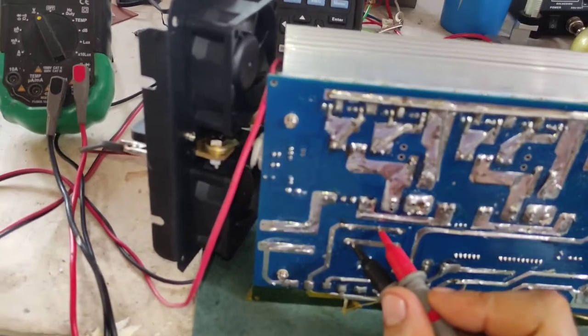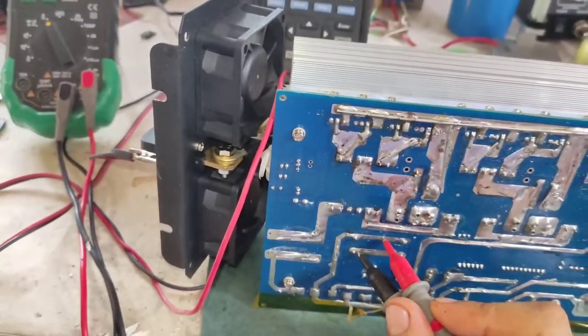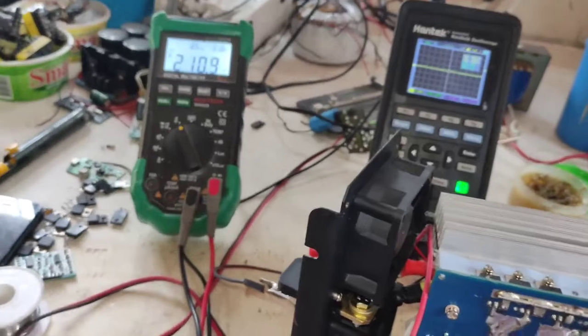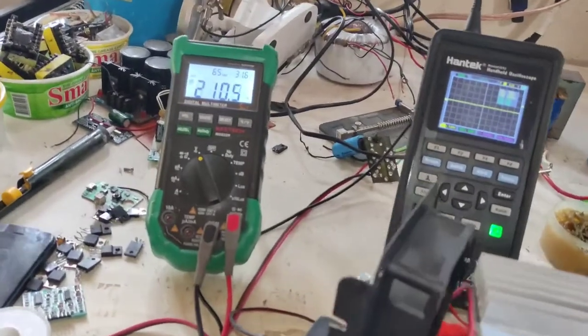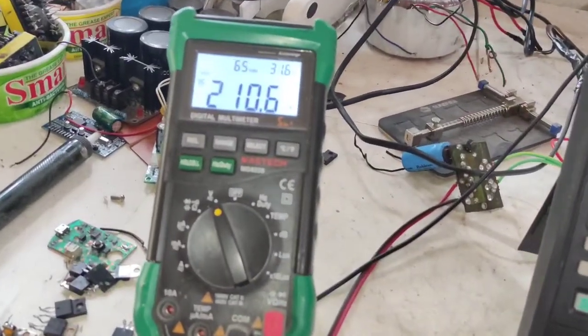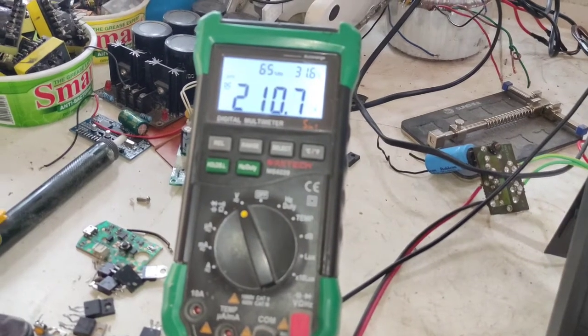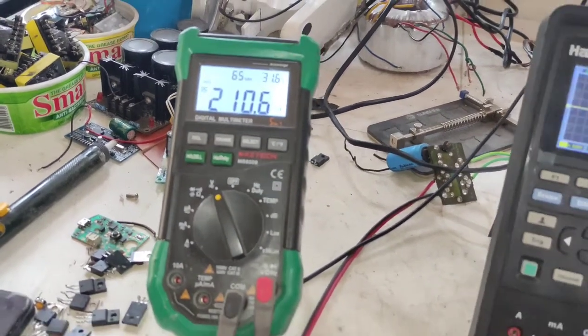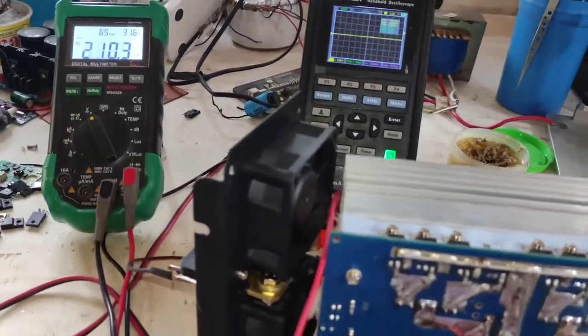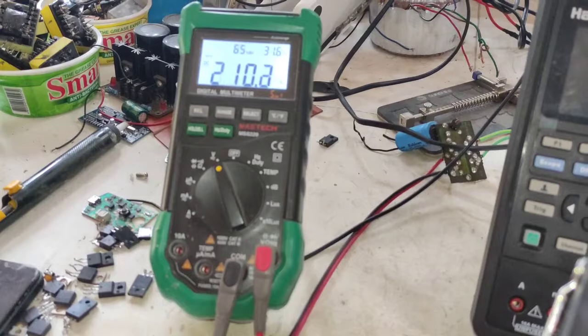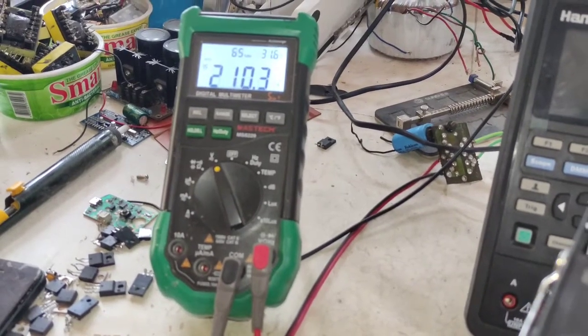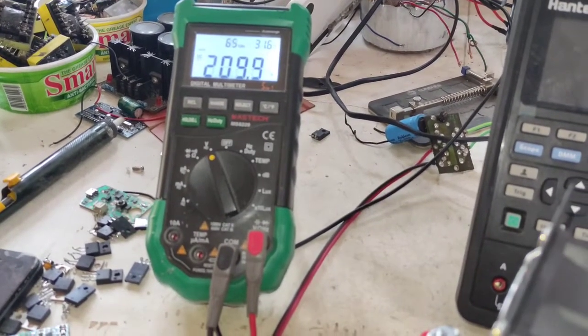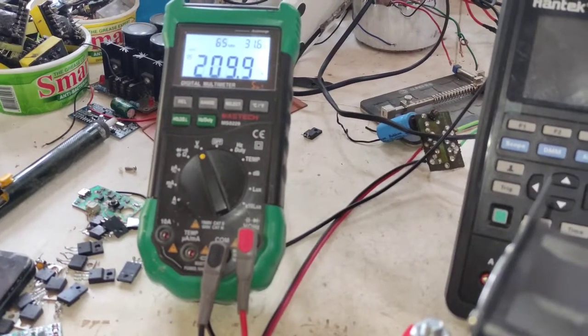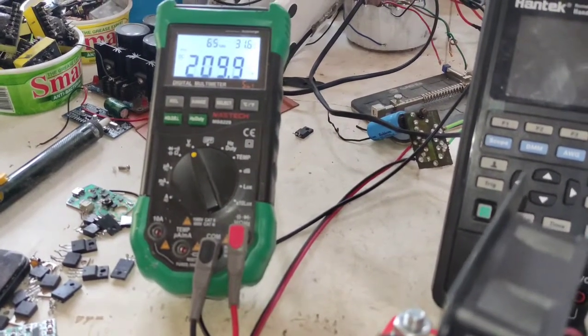Now the probe is connected, and here we have our DC voltage. That is 210 volts DC, which is 50% of the RMS value. It must be 320 or 380 volts here, but we have very low voltage on the caps. That means we have a problem in the feedback.